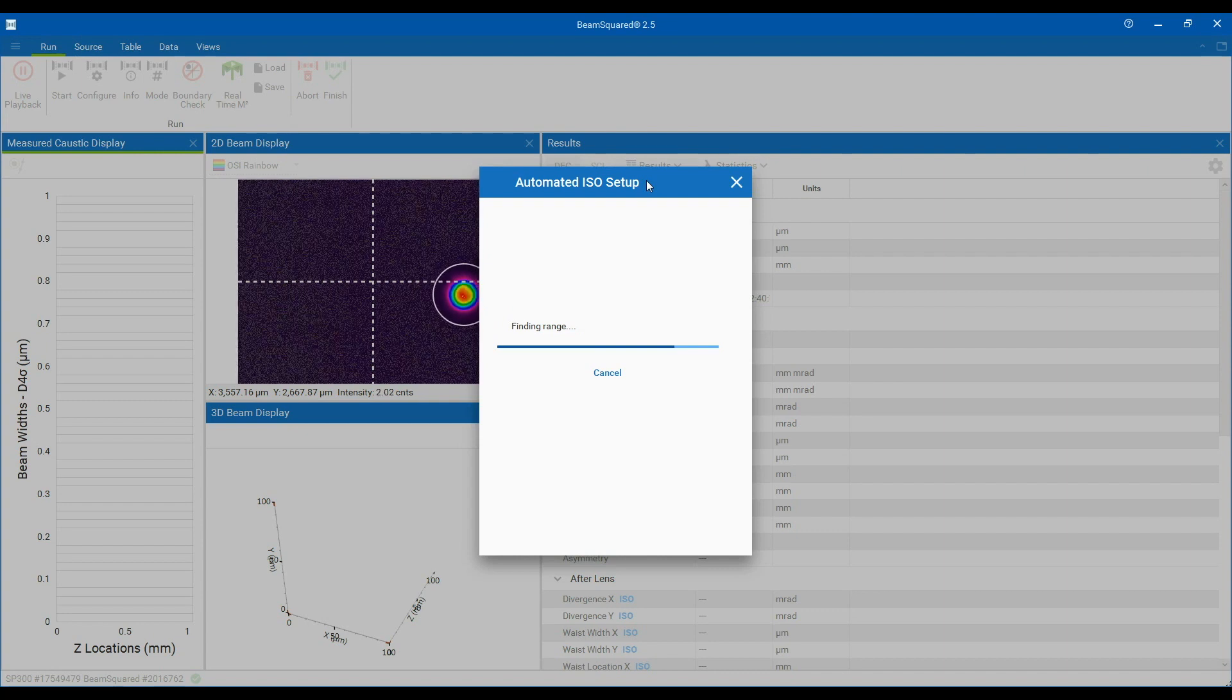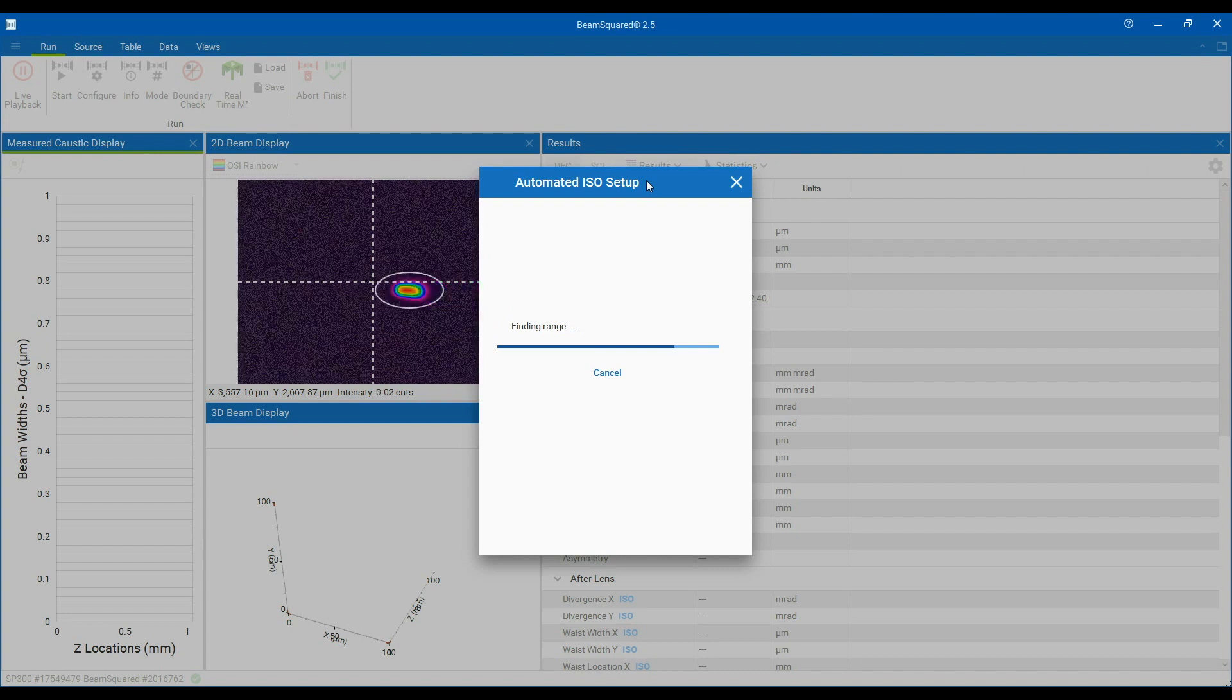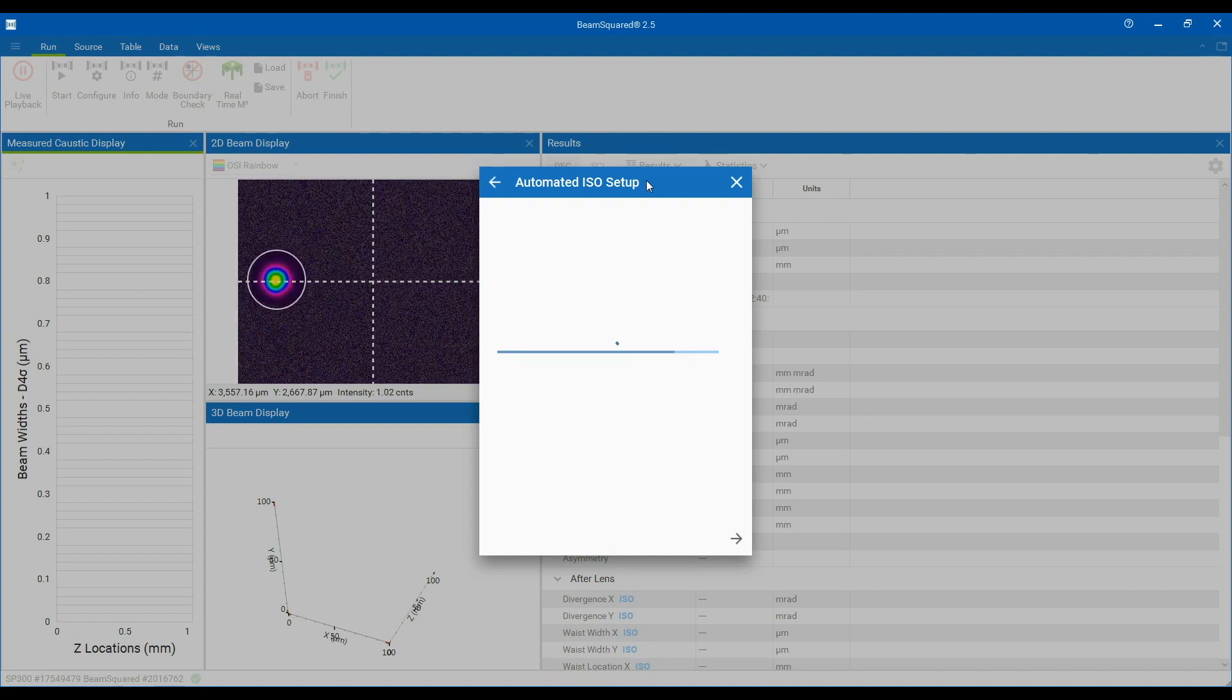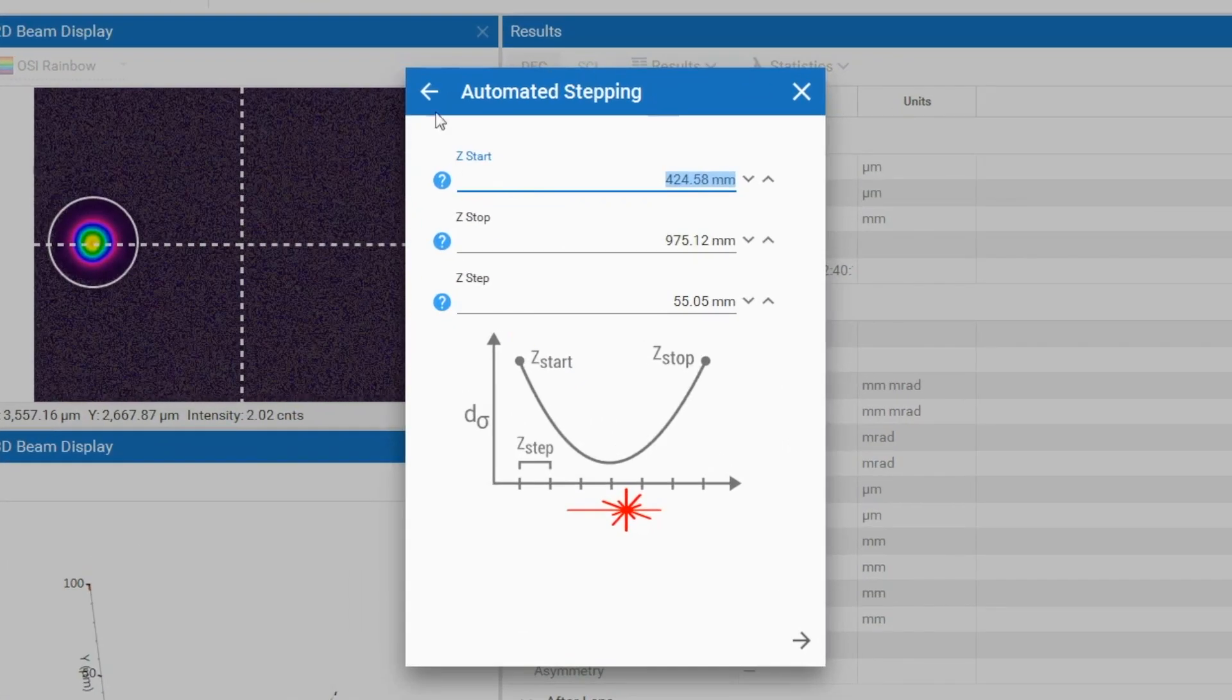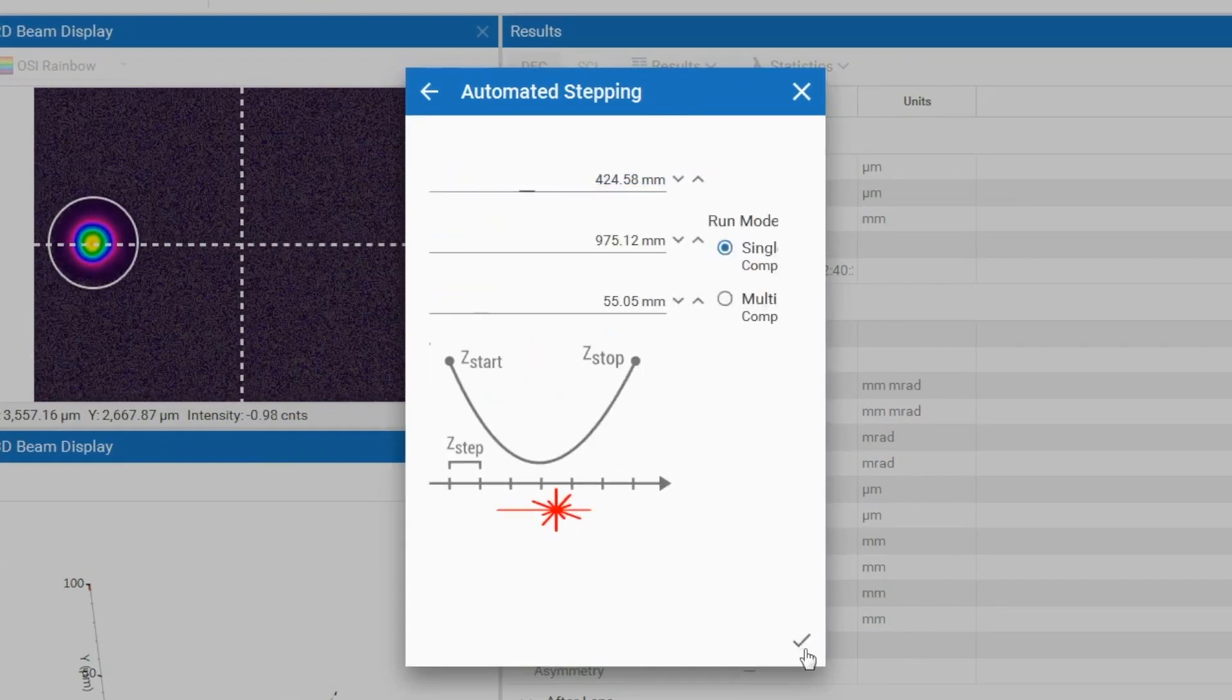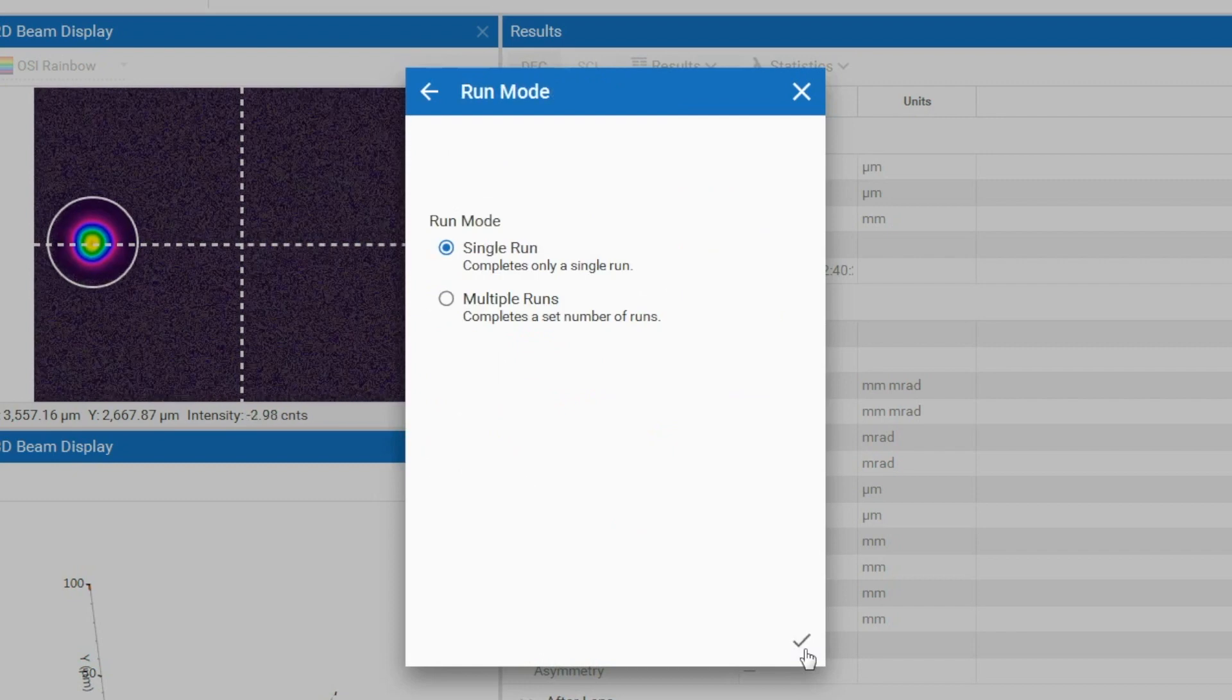If the automated ISO setup is unable to construct an ISO compliant beam propagation measurement, the application will go into automated stepping mode. The automated stepping mode only requires a start and stop location and a step size.